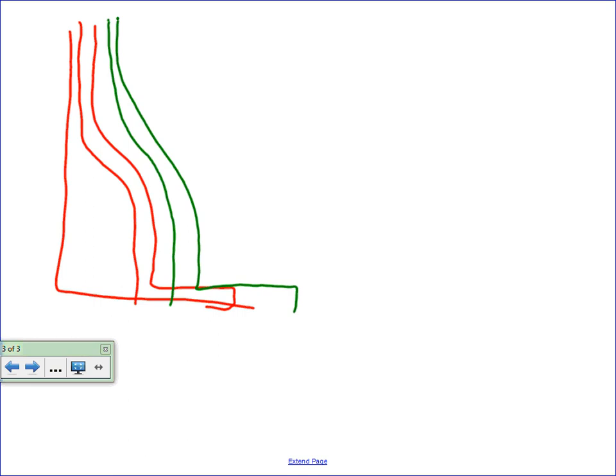If we're talking strictly like a thermal mag breaker, a thermal mag breaker uses a bimetal and a magnet internal. So the bimetal, as your current goes up, that bimetal starts deflecting, and when it gets to a certain point, it trips the handle mechanism and the breaker trips. Magnetic, it's like a coil with a plunger, and when the fault comes, bang, it takes that breaker offline right away.